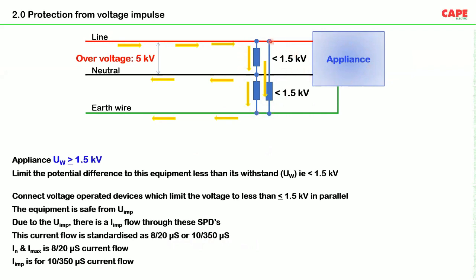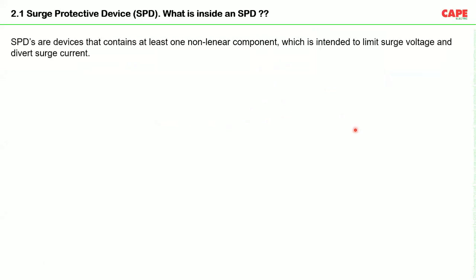We are making an SPD connected between lines and the earth, or between lines in some typical fashion, and these devices have a parameter called voltage protection level. These devices will limit the transient over voltage to that particular limit. As a result, your appliance is safe. This is what SPDs are about.